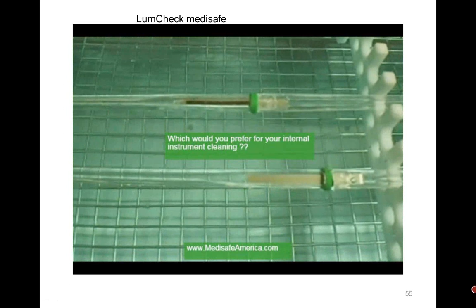Now, I have taken this off YouTube. It's out on the web. The company did use our product at that time, but that showed you if you put a lumen device and you did not hook it up to pulse flow, nothing is going to clean the inside of that lumen. That is just a great example, and I pulled that off of YouTube. It's public domain. So you do not put lumens and suctions like this. You hook them up to the special devices in your washer or your sonic to get that pulse flow. That is vital and important, and Michelle Alfa in her article stressed why you must do this.